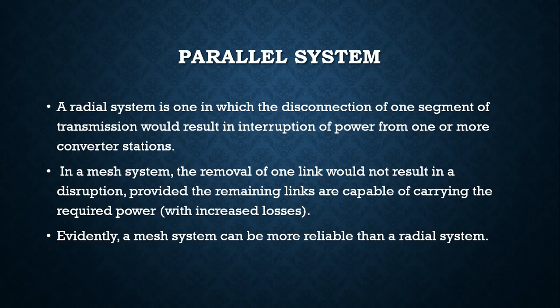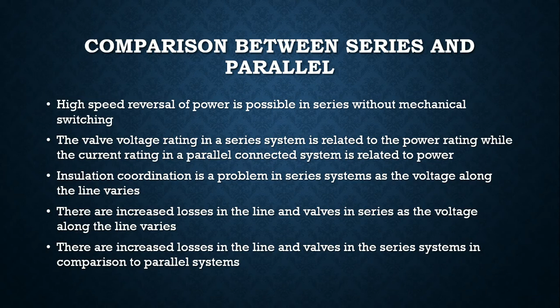Let us see a small comparison between series and parallel systems. High speed reversal of power is possible in series without mechanical switching. The valve voltage rating in a series system is related to the power rating, while the current rating in a parallel connected system is related to power. Insulation coordination is a problem in series systems as the voltage along the line varies. There are increased losses in the line and valves in series systems in comparison to the parallel system.